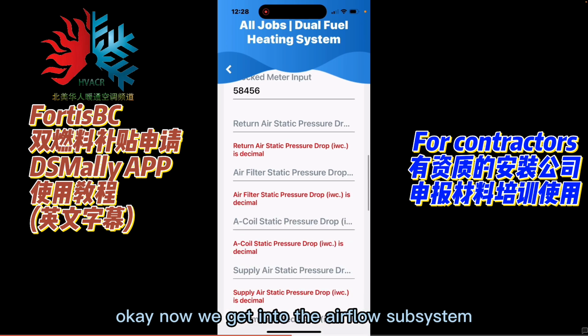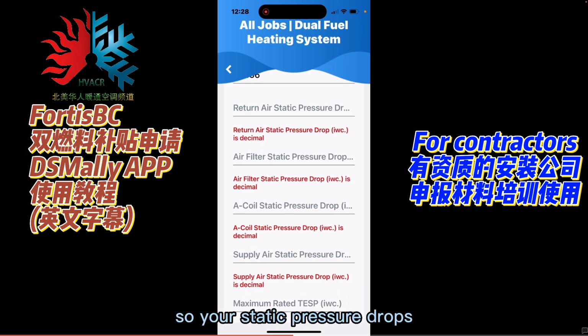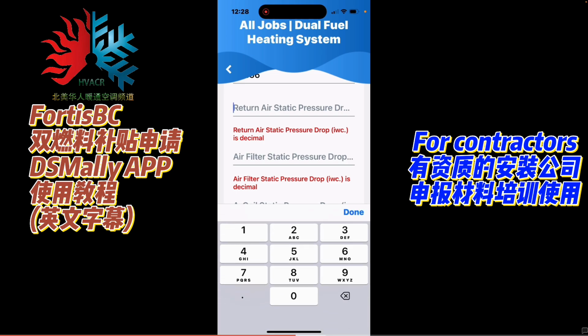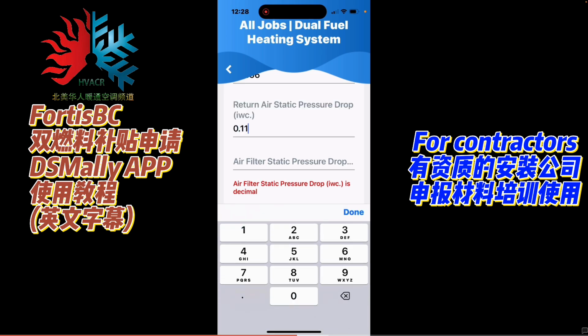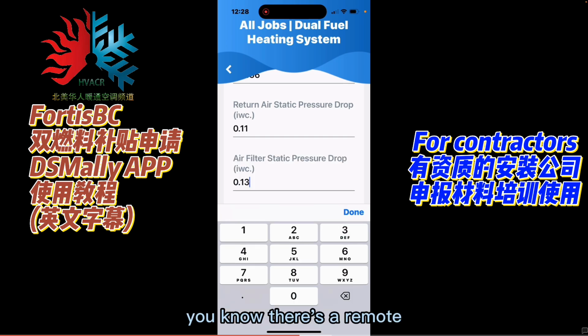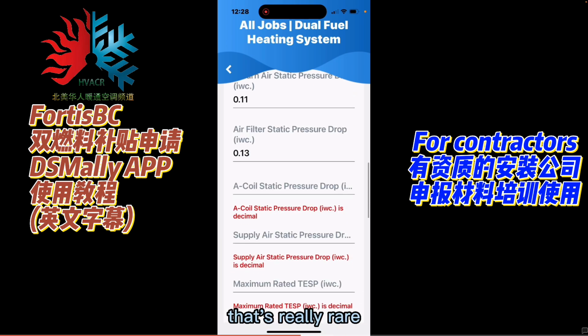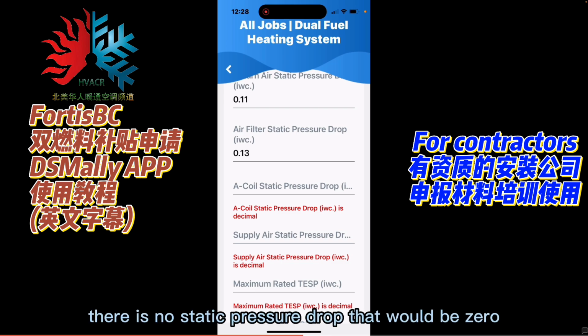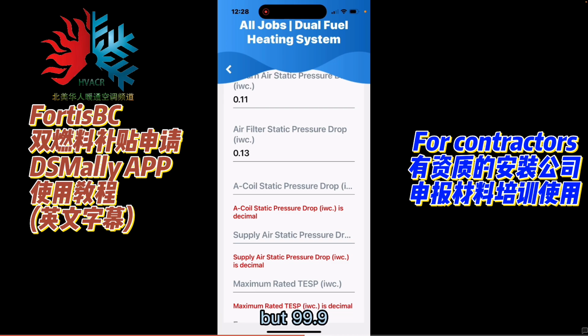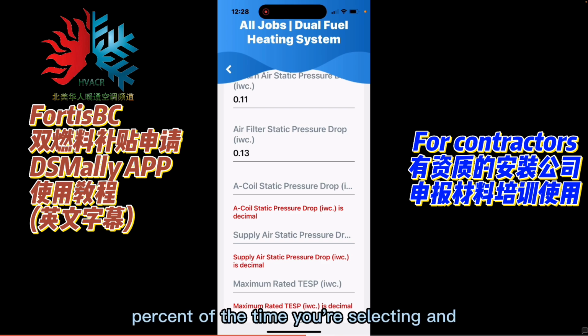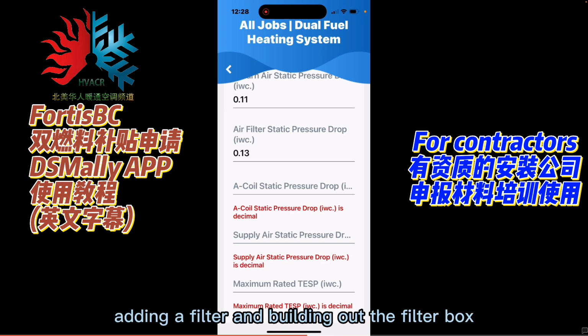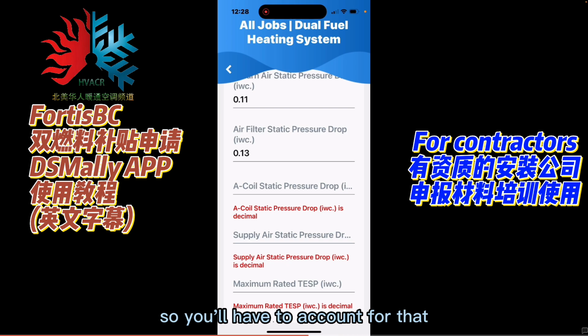Okay, now we get into the airflow subsystem, so your static pressure drops. So your return air, your pressure drop across the air filter. Now I know there's a remote chance that the filter may be internal. That's really rare. Obviously, if it is internal, there is no static pressure drop. That would be 0. But 99.9% of the time, you're selecting and adding a filter and building out the filter box. So you'll have to account for that air pressure drop there.